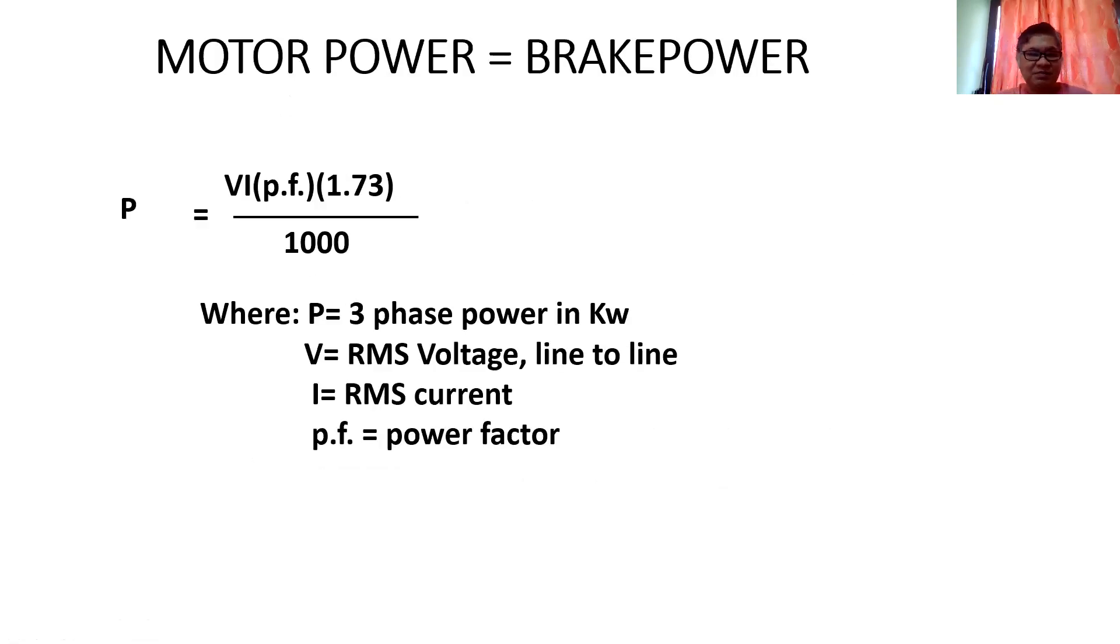The motor power or the brake power needed by the motor can be calculated as P equals V times I times power factor times 1.73 divided by 1000. Where P is three-phase power in kilowatts, V is RMS voltage line to line, I is RMS current, and p.f. is power factor.